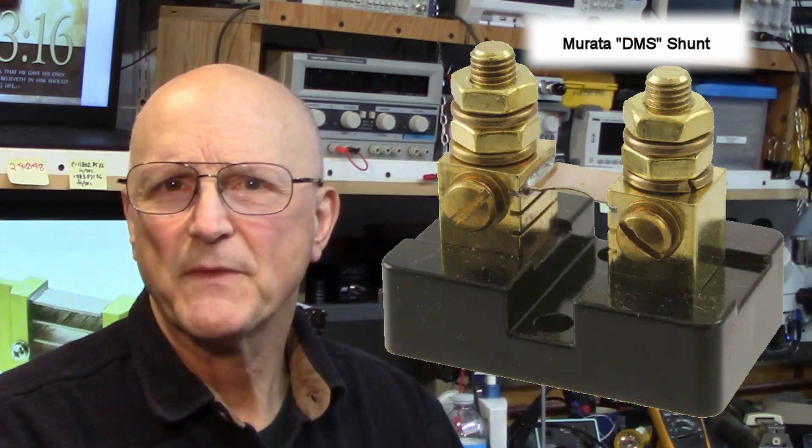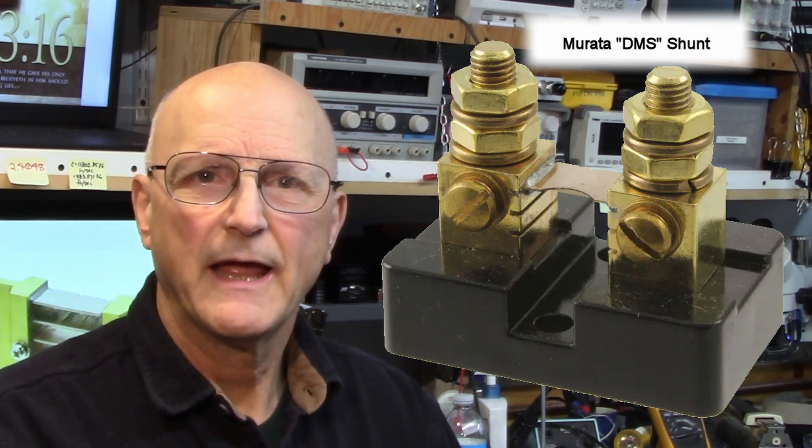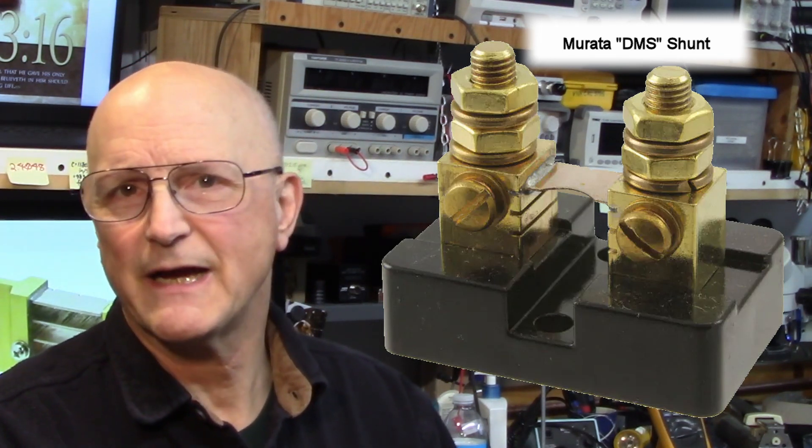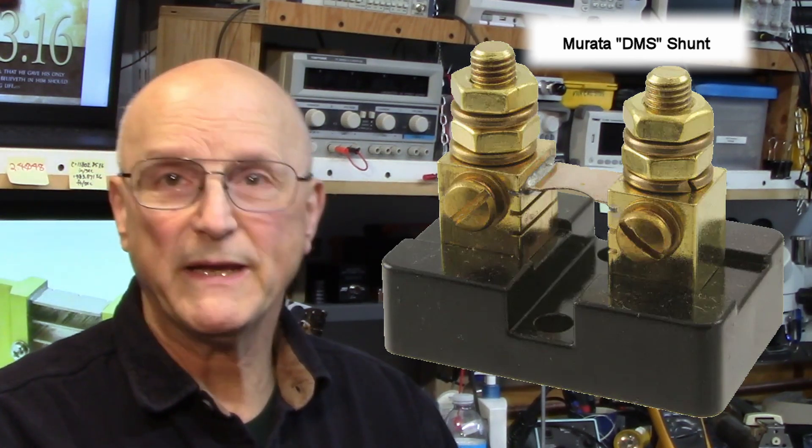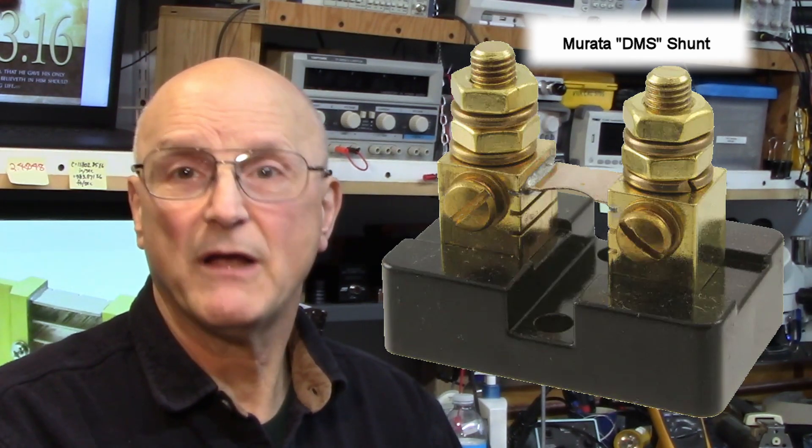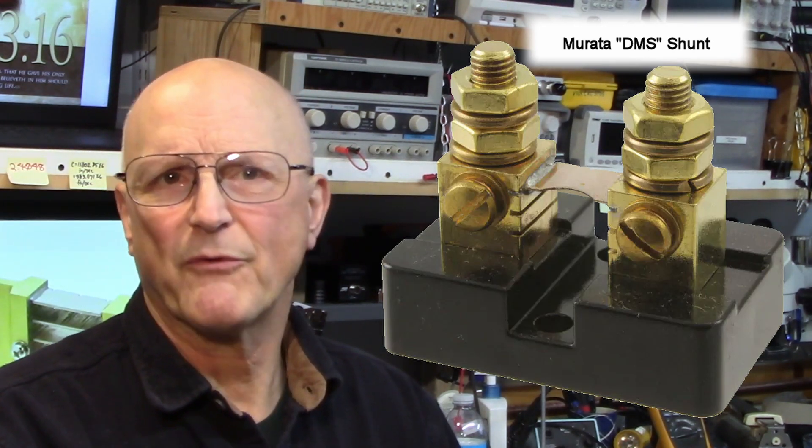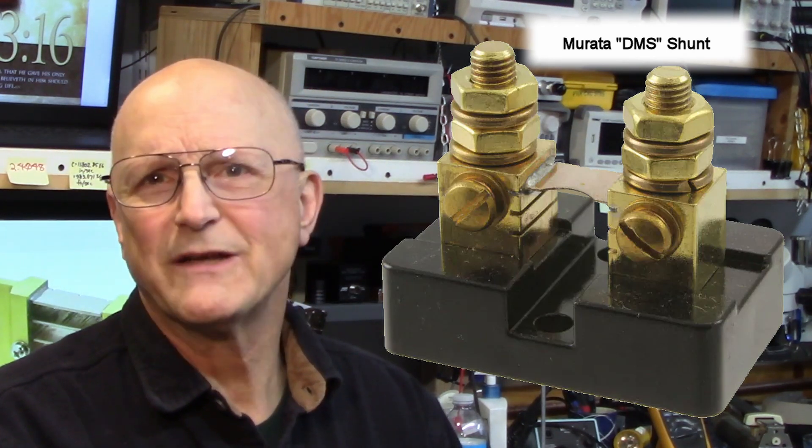While this is a conventional Kelvin connection, it isn't always quite so obvious what we're doing. Here's a case in point. The big bolts on the top are the current connections and the small screws on the side are the voltage connections. They're all on the same big block of metal. Now while we are making the same kind of connection, the separation between the current and the voltage connections are not quite so obvious.